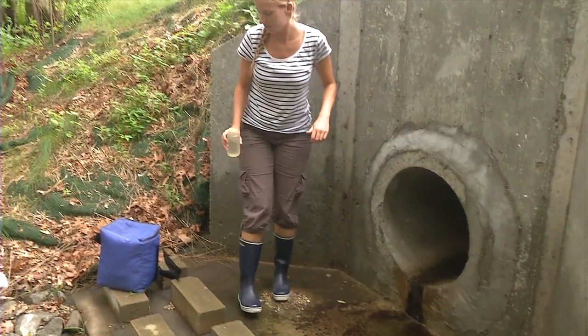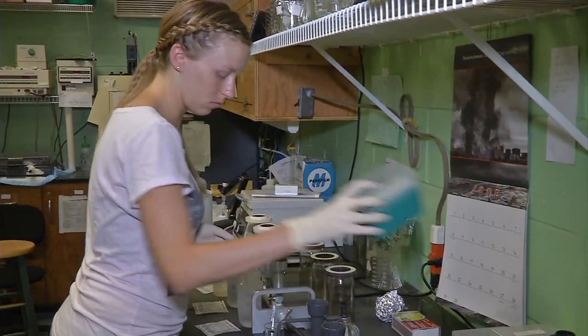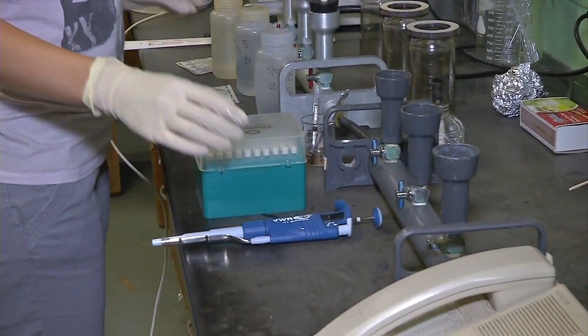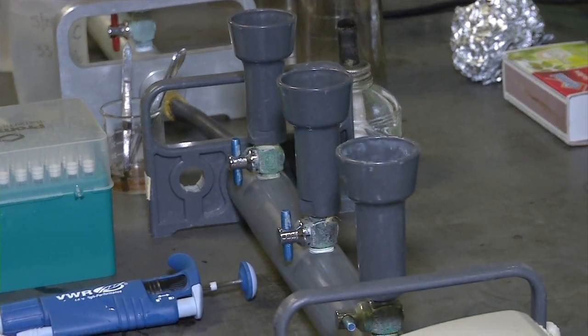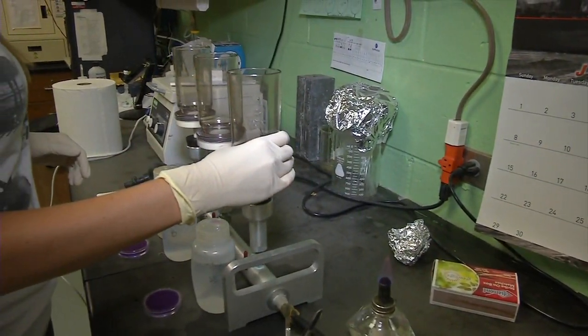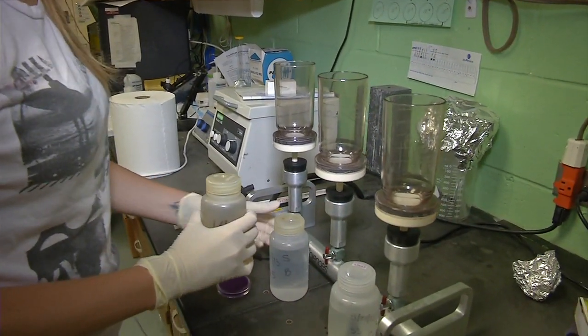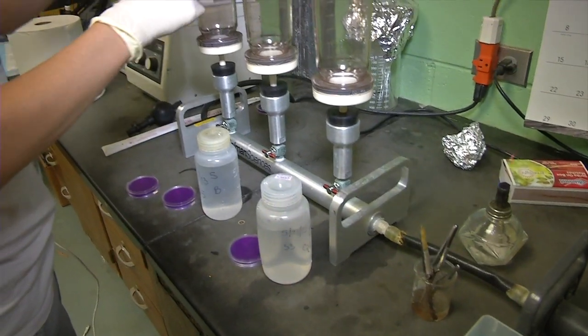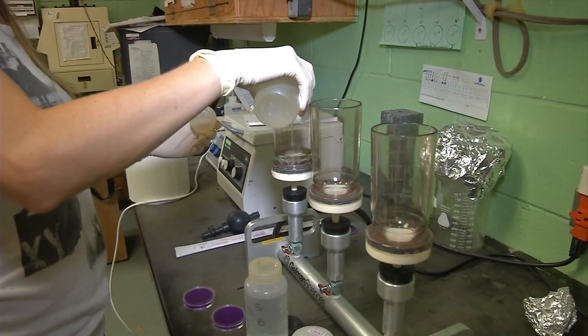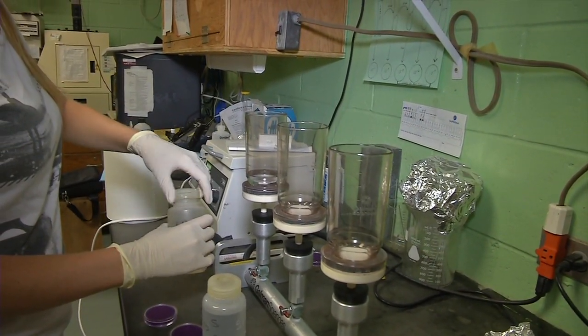When we talk about illicit discharge, that's when there's something coming out of the pipe that shouldn't be. All pipes, in this case the stormwater pipes, are meant to convey stormwater. Illicit means that there's something other than stormwater coming through that pipe. It could be someone who doesn't even know that they're tapped into the system. Sometimes with some of these older systems, before there were rules set in place, people didn't know what they were, and they just tapped into them as a way to get rid of their wash water or, in really bad cases, wastewater. So by detecting the amount of bacteria we're finding in water that could be illicit, in that it hasn't rained in 48 to 72 hours, we can backtrack and detect where that may be coming from, to better manage what's going into the bays and also fix a problem that could be getting worse.